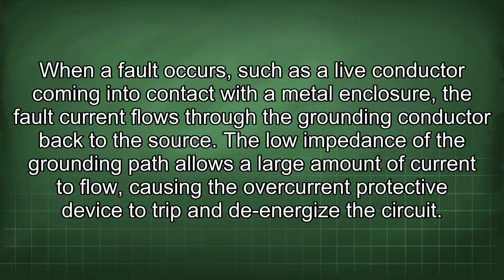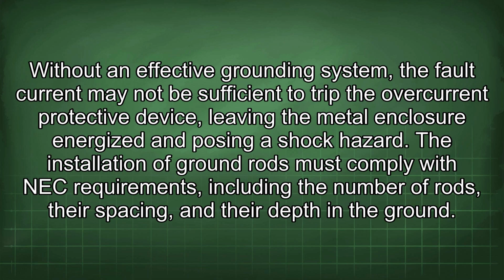When a fault occurs, such as a live conductor coming into contact with a metal enclosure, the fault current flows through the grounding conductor back to the source. The low impedance of the grounding path allows a large amount of current to flow, causing the overcurrent protective device to trip and de-energize the circuit. Without an effective grounding system, the fault current may not be sufficient to trip the overcurrent protective device, leaving the metal enclosure energized and posing a shock hazard.